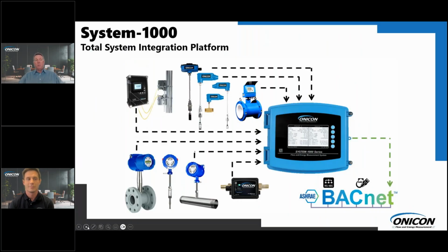So we consider the System-1000 to be a total system integration platform. As you can see, any of these ONICON products that we just mentioned from the ONICON family of products can be connected to the System-1000, whether it's a clamp-on ultrasonic, insertion electromagnetics or turbine meters, inline electromagnetics, steam meters, gas meters, inline ultrasonics. All of these ONICON products and more can be connected to your building automation system through a System-1000, with information sent to your building automation system over BACnet serial RS-485 and IP.